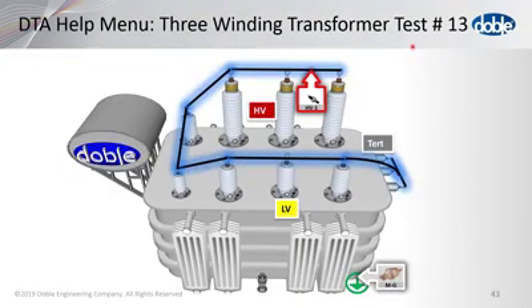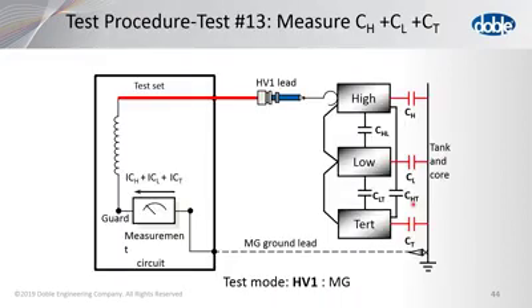Now, also for test number 13, of course, we have to go back up on top of the unit again to put the shorting jumpers on, to connect the HV. Of course, the HV1 is already here, but we have to take the HV2 down, the M3 cable down, and then disconnect it from the M7100. After we have this set up, of course, we are doing these tests here. We're energizing all of the windings at once. Be careful with the voltage again, and we'll measure CH plus CL plus CT.